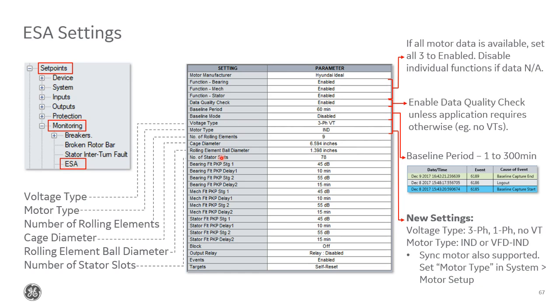The next handful of settings here are more motor information. These need to be obtained from the motor data sheets, and these generally aren't from the standard data sheets. You might need to go back to the motor manufacturer and ask for more info. These would be things like the number of rolling elements in your bearings, the cage diameter of the bearings, and the rolling element ball diameter. Again, these are directly from the bearing data sheets. And then often you can find the number of stator slots on your general data sheets.